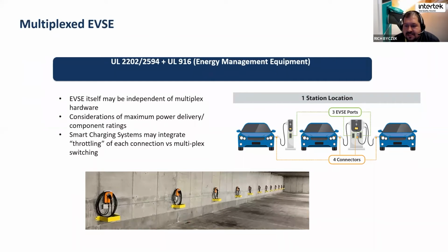I'll note that some systems, like the image on the right, if they're all fed from a single power source that has to be multiplexed, then this would take precedence. If the system on the right that has those 3 EVSE ports, maybe a CHAdeMO and an SAE type connector, is all completely handled on board that system, then this wouldn't necessarily apply. That would just be evaluated as part of the EVSE.